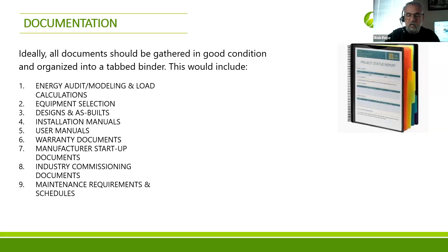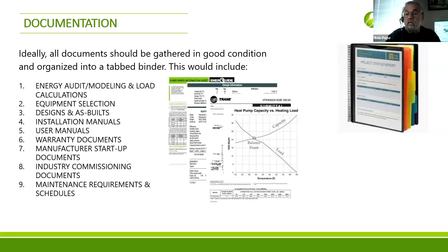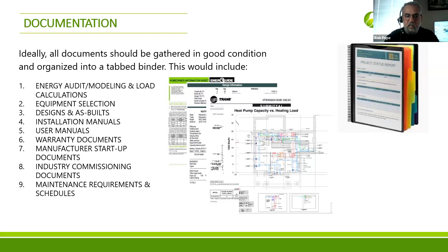The energy audit modeling, load calculations. It should include the documentation for equipment selection, which would be submittals and the balancing calculations. It should also include the design and any as-built variations during construction that were accepted from the design, so that if down the road a technician is troubleshooting a problem, they want to know where everything is behind those walls and ceilings.